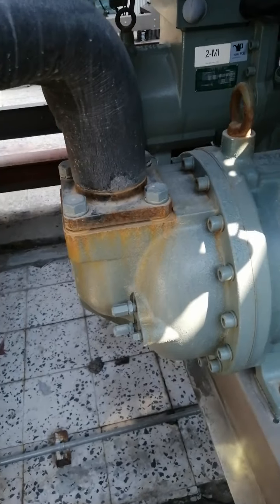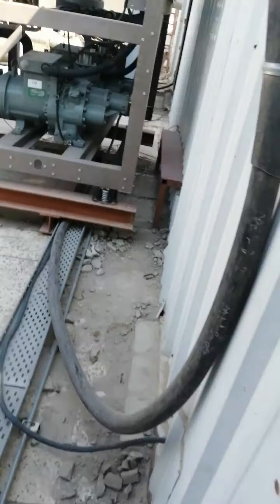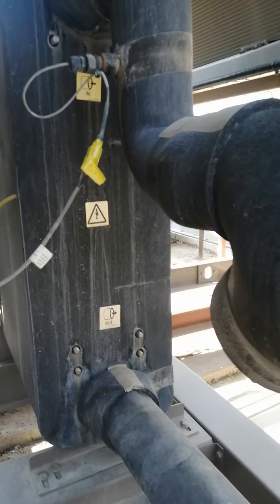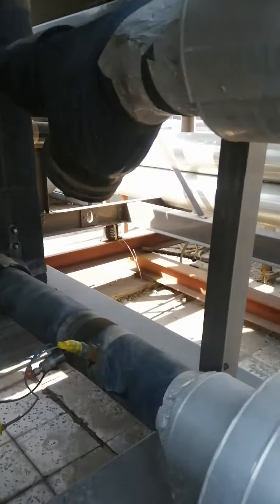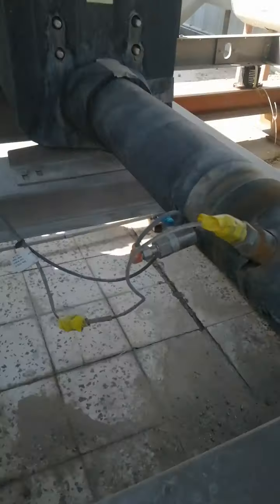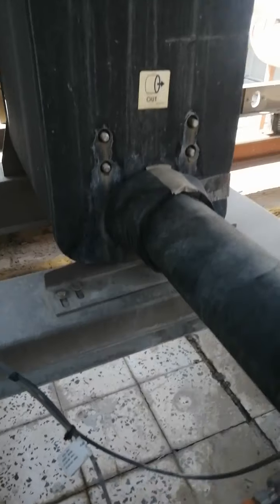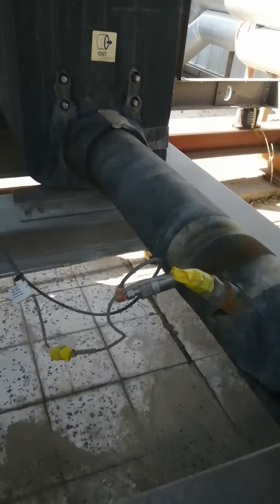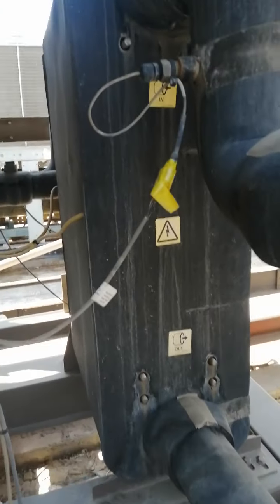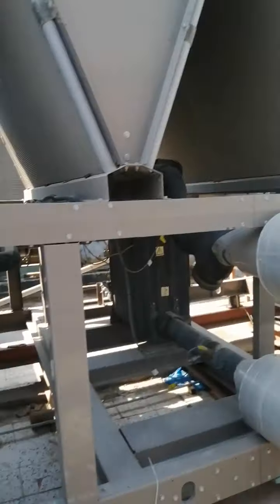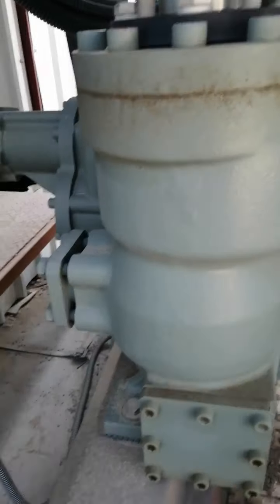Okay, now on the other side I will show you the water pipeline which connects to the plate heat exchanger. This is the water pipeline. You see, this is the plate heat exchanger. Water coming and water going. This is the pressure switch and this is the temperature switch. You see, pressure sensor and temperature sensor. Sorry, this is a pressure temperature sensor. This is the temperature sensor and this is the pressure sensor of the chilled water pipeline. Okay, so there is nothing typical. Very easy. This is very easy.